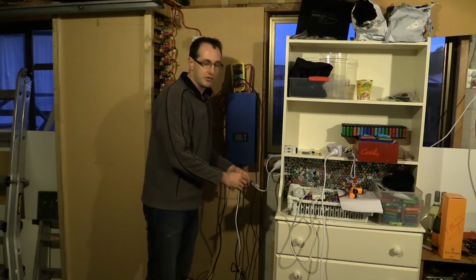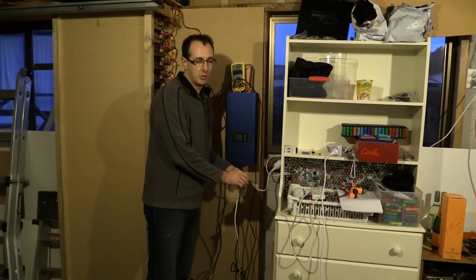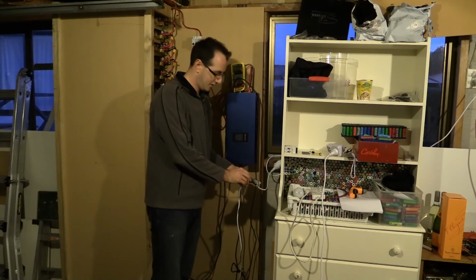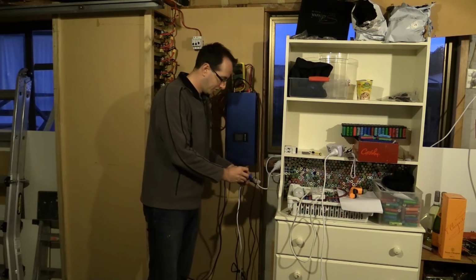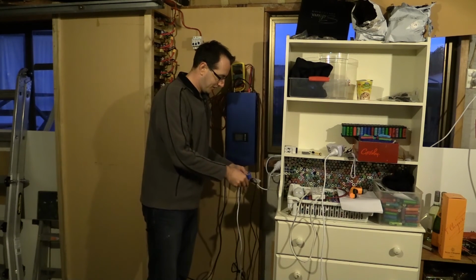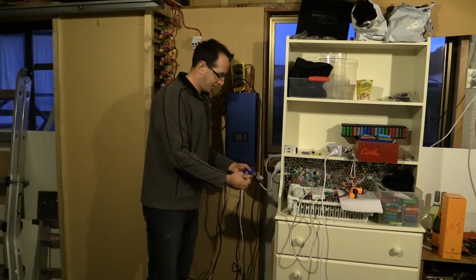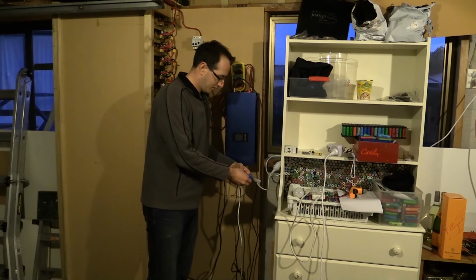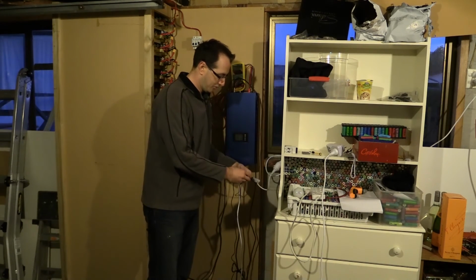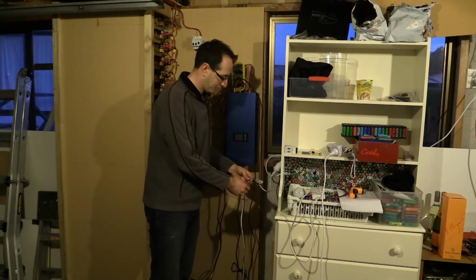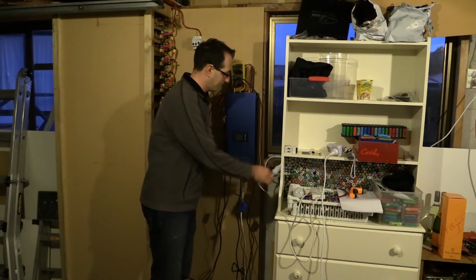This is how you kind of trick the CT clamp into thinking that there's more load than you've actually got plugged in. You just wind it around multiple times. It's a great way of testing, especially when you want to get over 2,000 watts. It's easier to just wind it around twice and you end up with 4,000 watts across the CT anyway.